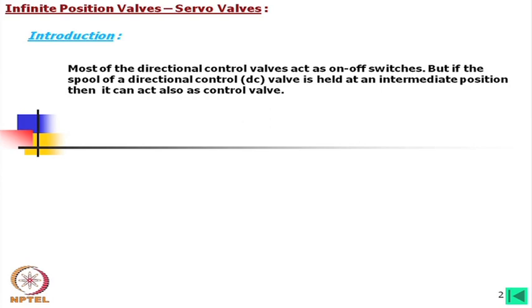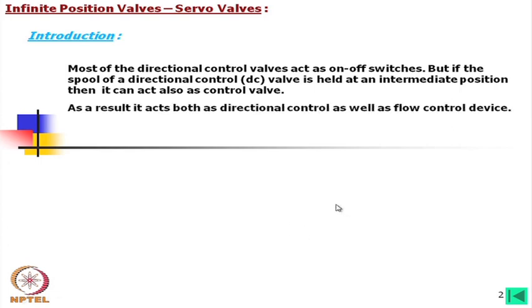Most directional control valves act as on/off switches, but if the spool of a directional control valve — also called a DC valve — is held at an intermediate position, then it can act as a control valve, meaning infinite position control. On/off is just 1 or 0; intermediate positions allow control of both flow and pressure. As a result, it acts both as a directional control and as a flow control device.